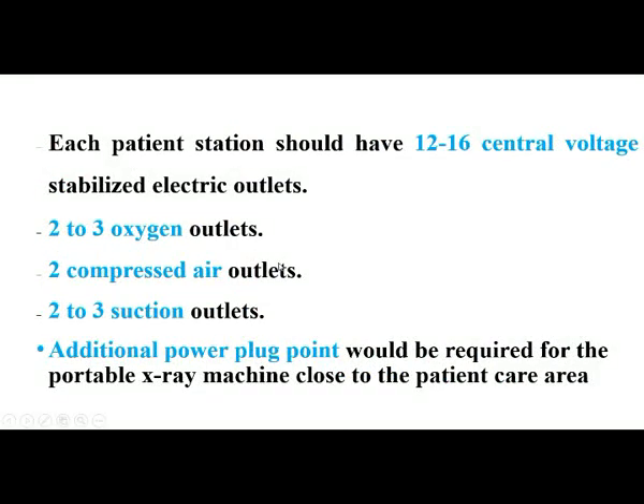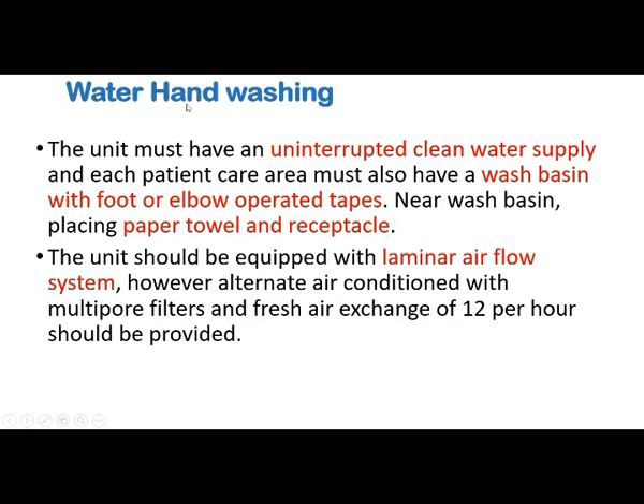Each patient station should have 12 to 16 central voltage stabilized electrical outlets, 2 to 3 oxygen outlets, 2 compressed air outlets and 2 to 3 suction outlets. An additional power plug point would be required for a portable X-ray machine close to the patient care area. That is the physical setup.